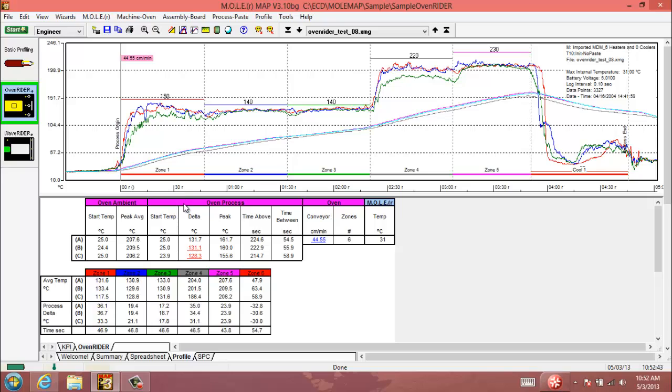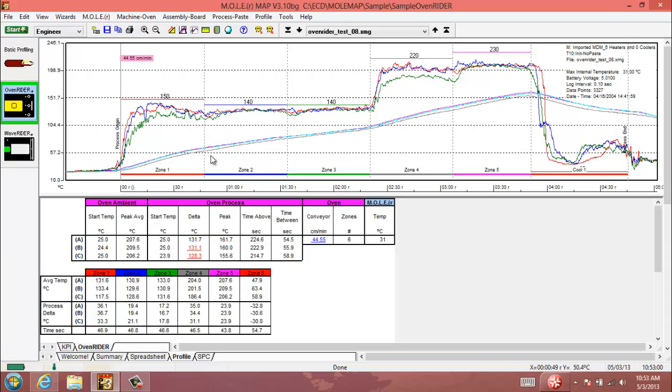We can get an entire temperature delta for our Oven process, which is basically the temperature change in the process sensors from the beginning of Zone 1 all the way to their peak temperature at the end of Zone 5 in this example. And so that will be displayed for you here for each sensor across the zones.